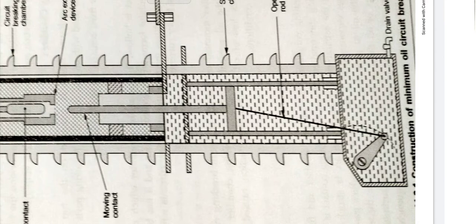Let's see first the supporting chamber. This is the bottom chamber which is made up of porcelain and mounted on metal chamber. It is filled with oil which is physically separated from the oil in circuit breaker chamber. The oil inside the supporting chamber and the annular space formed between the porcelain insulation and bakelized paper is employed for insulation.